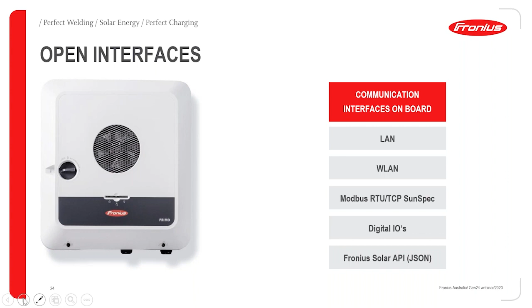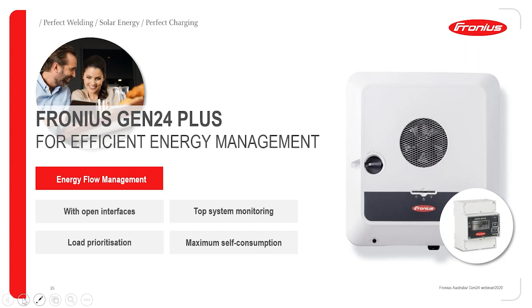What this means is you have a Fronius smart meter in the main switchboard, and if, for example, you have excess energy, you can say, okay, turn this load on using an external contactor. You can choose, for example, four different contactors to turn on and off, and you can say this one turns on first, then the second one, then the third one. So it gives you a lot of flexibility. This energy flow management usually works with big loads, like your hot water system, your pool pump, stuff like that. That's where people will usually use this energy flow management.